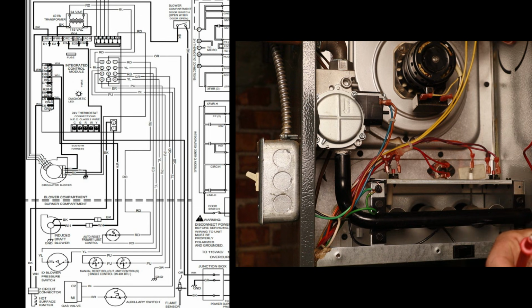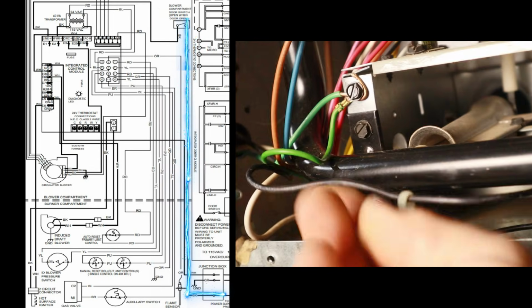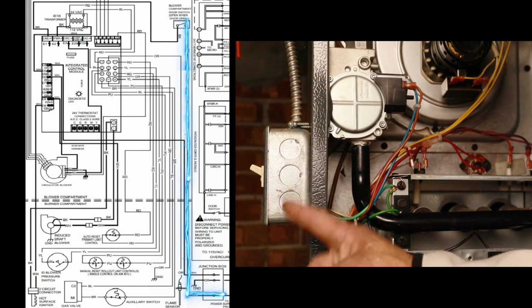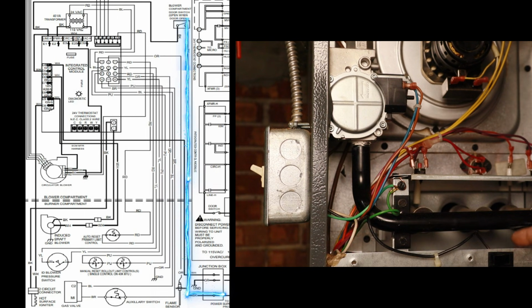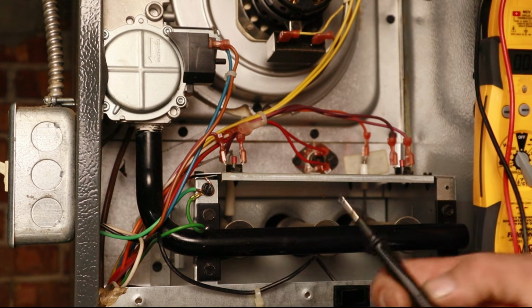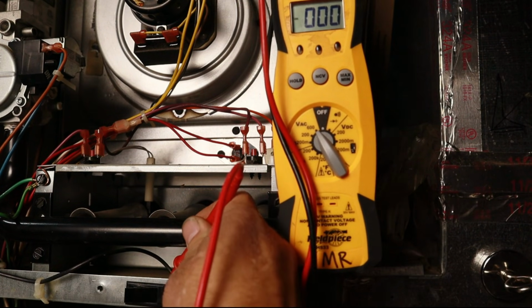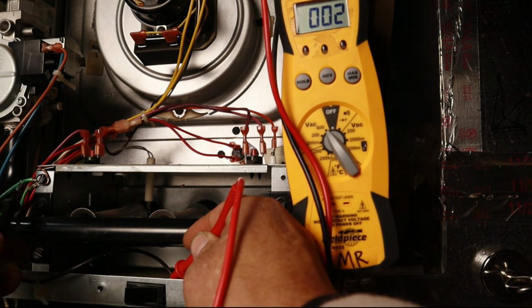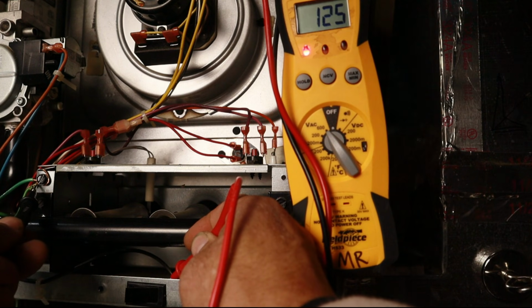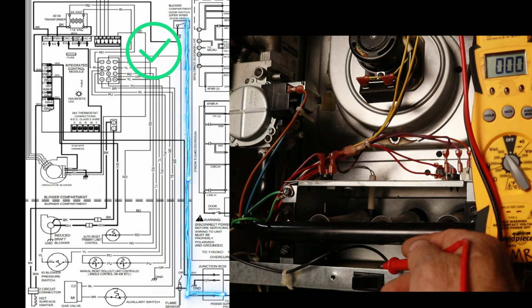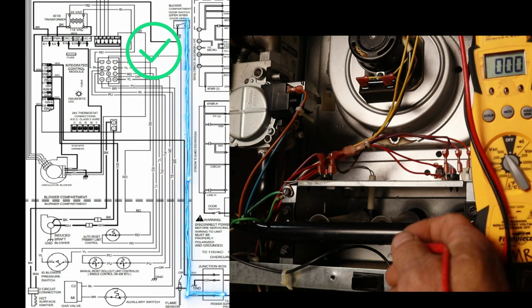Now going back to our diagram, we can see that black wire brings us right to a blower compartment door switch. So that's our door switch right here. When we follow this black wire right here, we can see it brings us right to our door switch. So as long as this switch is on, which it is right now, I should have 115, 120 coming up to this switch. Now you're not always going to read exactly 115 or 120 as it's stated on the diagram. You're going to have a little bit of variance there. So let's take our multimeter, we'll put it on VAC. I'm going to take my probe and put it on the door switch terminal there, and I'd take the other one, put it on ground, and you can see I'm reading 125. So I know I'm good all the way up to this door switch. My breaker is not tripped, my power is on, and I'm good up to this point.